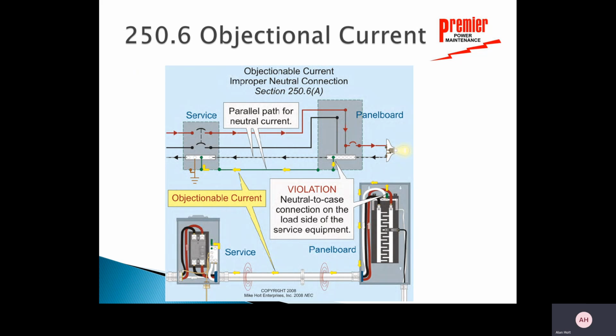So let's look at some objectionable current. So we'll look at a couple of examples where there are violations. So here's the top one. We've got a light here, incandescent light, 120 volts, I assume. But if I notice right here in its neutral bus, I've got a connection to ground right there. And I've got a connection to ground back here at my service.